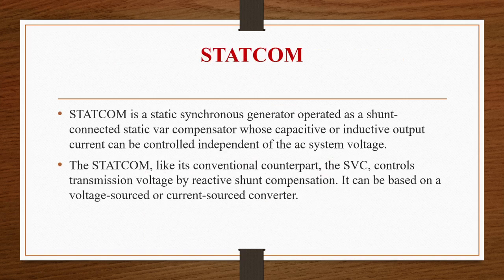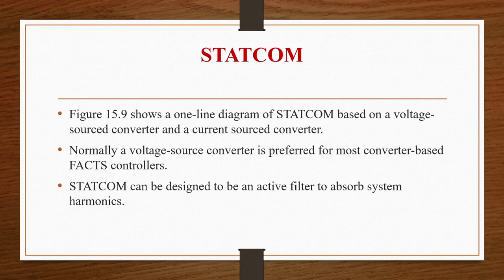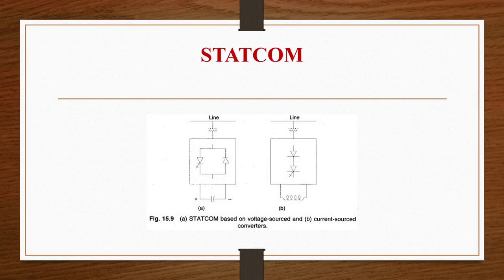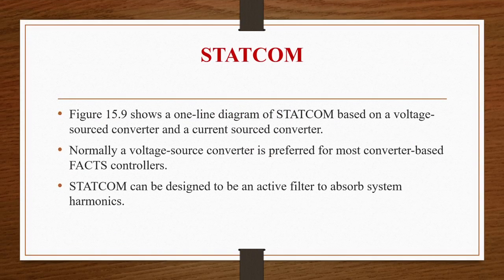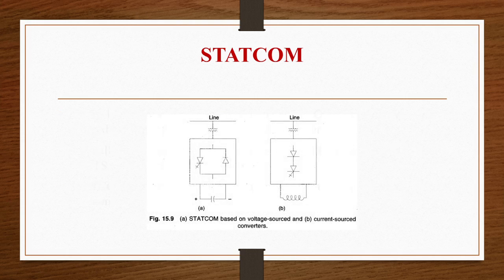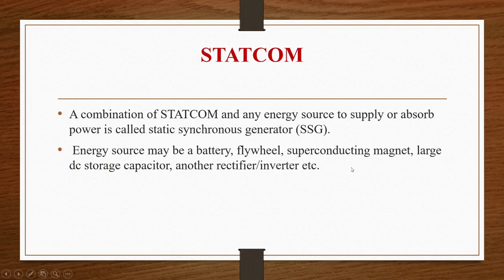Now let us see STATCOM — static synchronous compensator. STATCOM is a static synchronous generator operated as a shunt-connected static VAR compensator whose capacitive or inductive output can be controlled independent of the AC system voltage. STATCOM, like its conventional counterpart, controls the transmission voltage by reactive shunt compensation. It can be based on a voltage source or current source converter. Normally a voltage source converter is preferred for most converter-based VAR controllers. STATCOM can be designed to be an active filter to absorb system harmonics. A combination of STATCOM and any energy source to supply or absorb power is called a static synchronous generator (SSG).